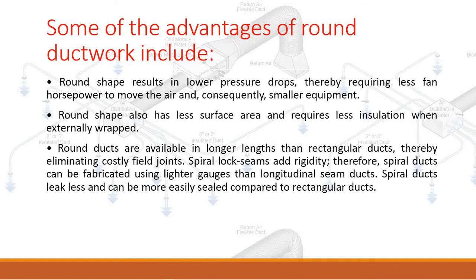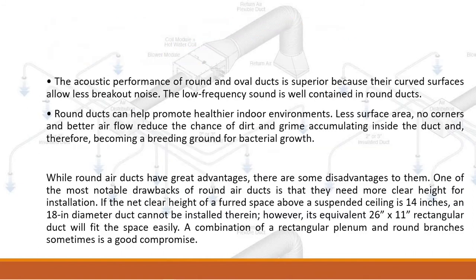The acoustic performance of round and oval ducts is superior because their curved surfaces allow less breakout noise, and low frequency sound is well contained in round ducts. Round ducts can also help promote healthier indoor environments — less surface area, no corners, and better airflow reduce the chance of dirt and grime accumulating inside the duct and becoming a breeding ground for bacterial growth.